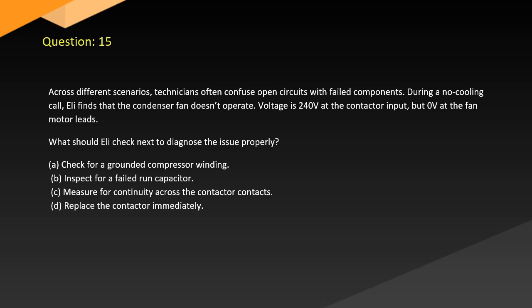Voltage is 240 at the contactor input, but 0 at the fan motor leads. What should Eli check next to diagnose the issue properly? A. Check for grounded compressor winding. B. Inspect for failed run capacitor. C. Measure for continuity across the contactor contacts. D. Replace the contactor immediately.